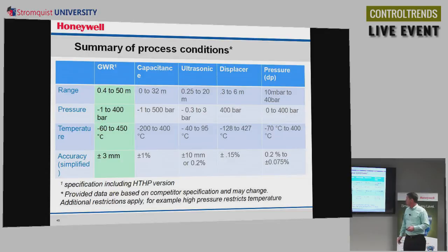And here's a table that compares and contrasts the different technologies we talked about: guided wave radar, capacitance, ultrasonic, the displacer, and differential pressure. They have different ranges. The guided wave will go up to 50 meters. And different pressures. Ultrasonic is not going to work in real high pressures, temperature variations and things, and different accuracies. So really, what I want to show here is that there's a lot of different ways to measure level. There are pros and cons to each one, and these are just things to keep in mind when you're advising your customers.